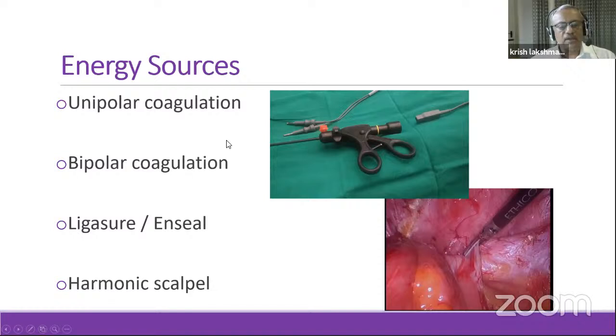To overcome that, you can use bipolar coagulation, which is very nice. The current passes just between the two lips, or tips, of the two blades of your bipolar cautery instrument, so collateral damage from current passing elsewhere is practically eliminated, completely eliminated.